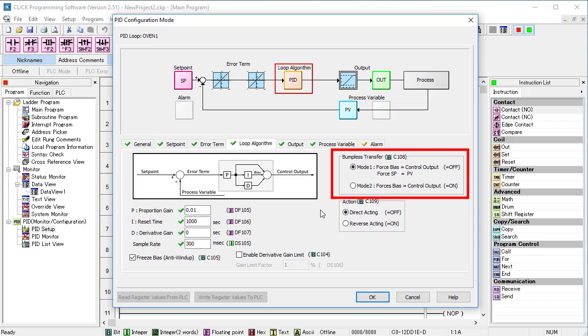The Bumpless mode is important to understand for Auto-Tune. When the system switches from manual to auto mode, if there is a big difference between the setpoint and the process variable, PID is going to try and correct the error as fast as it can by making big changes to the control output.